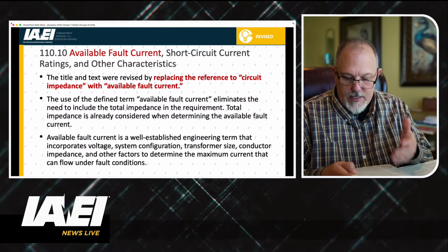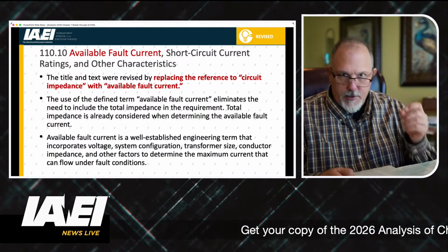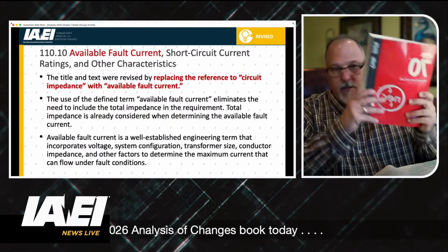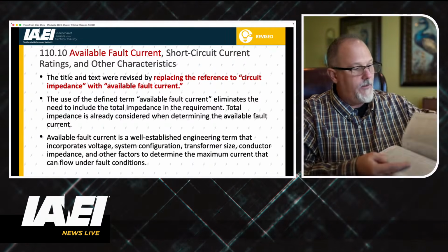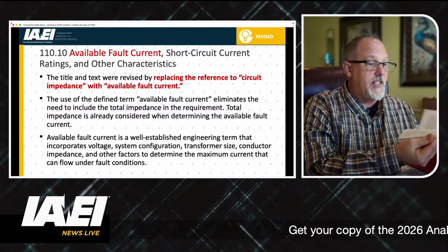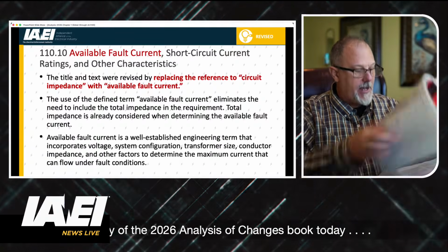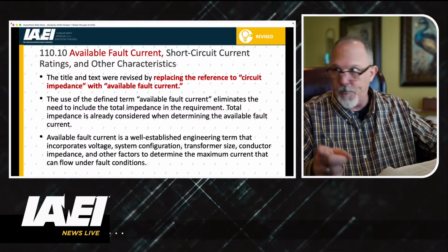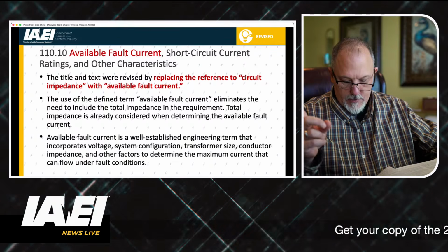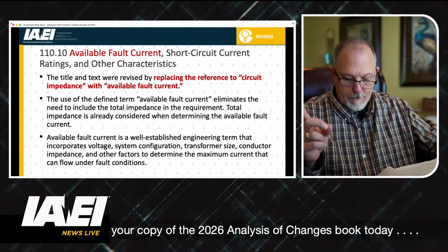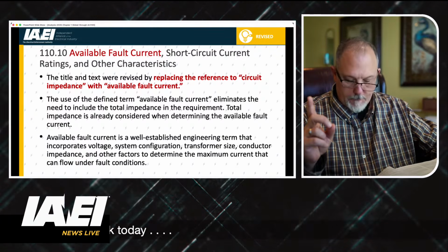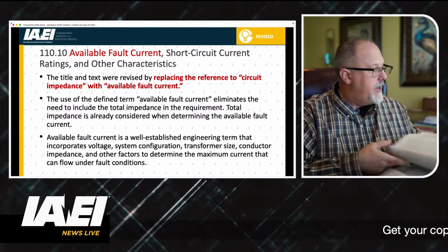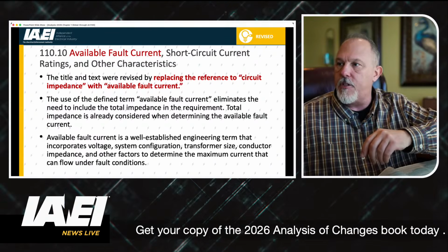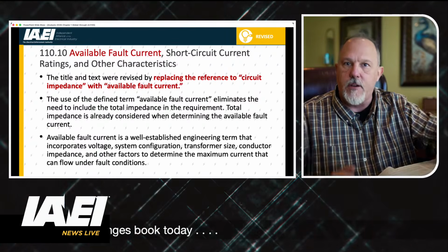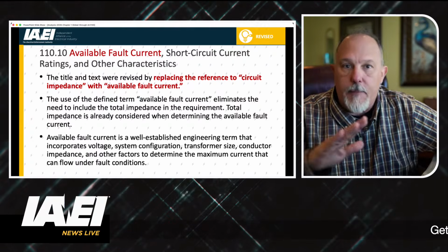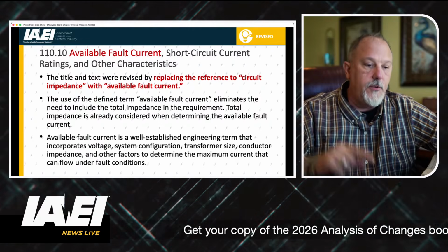So what we used to say in 110.10 was circuit impedance, short circuit current ratings, and other characteristics. Now, they changed it in the 2026 code, and wow, the definitions are getting larger. So 110.10 is now available fault current. They replaced circuit impedance with available fault current, and they changed some words in there. It still means the same, but I think the shift, instead of saying overall impedance and focusing on available fault current, makes a lot more sense. But I would not say that because of the change in 110.10, you're going to do anything different.